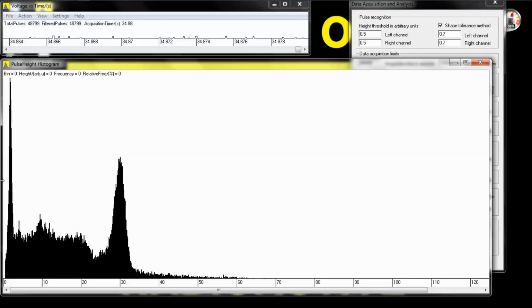Basically, you have counts going up and down. This is the y-axis, and it's counts. This is the x-axis, and it will be energy, from low energy on this side to high energy on this side. I already know what these energies are because I'm familiar with looking at these. This peak right here is 32 kiloelectron volts. This peak right here is the primary photopeak for cesium-137. Technically speaking, barium-137m, but whatever, cesium-137, and it's at 661.66 kiloelectron volts. There you go, cesium-137 right on the dot.